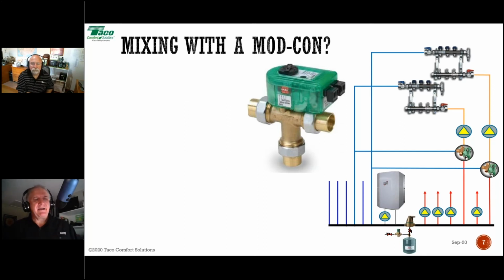But let's say you have 3 loads on your system. So you've got basement radiant in the slab. You've got between the floor joist radiant in upper floors, and then you have some radiators or some base. Let's call it some radiators, some panel radiators. Okay, so you've got 3 distinct and separate water temperatures.